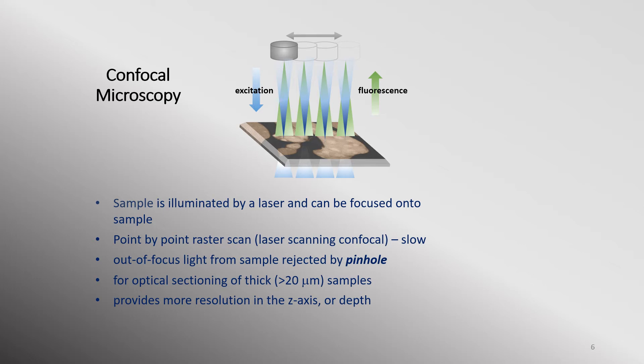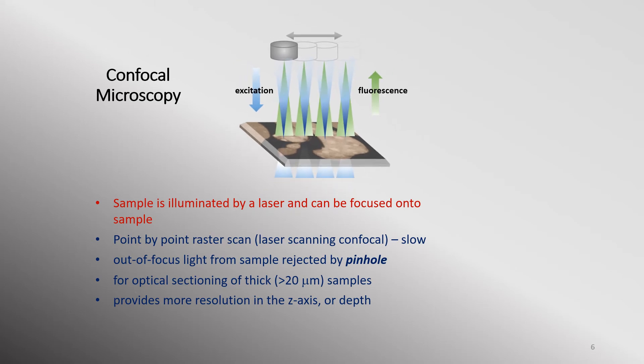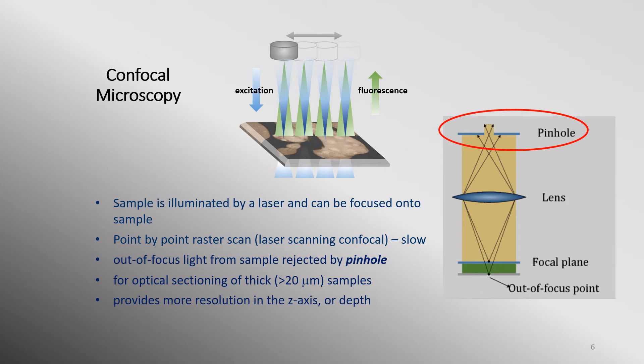A confocal microscope has the excitation source scanning with a focused beam of light across the specimen in a point-by-point raster pattern to form a complete image of the focal plane. Point scanning coupled to a pinhole spatial filter at a conjugate image plane is an essential feature of the confocal microscope. Together, they combine to remove most out-of-focus light. The background rejection from confocal techniques is helpful for tissue and thick specimens because this allows extremely thin optical sectioning, enabling structures and intracellular features deep within the specimen to be viewed. The main difference in resolution between wide-field and confocal comes not in the XY plane, but along the Z-axis.